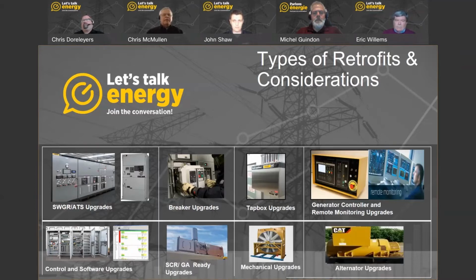Alternator upgrades. Alternator upgrades are rare in the standby application, but prime power in harsh environments offers challenges. Alternator upgrades to form wound versus random wound will live longer in a salt-laden atmosphere near the East Coast or aggregate applications with abrasive dust entrained in the air being drawn through the alternator for cooling. Often with alternator failures, we can help out with a failure analysis, and recommendations are made for this type of upgrade. So I'll hand it back to you, Chris.